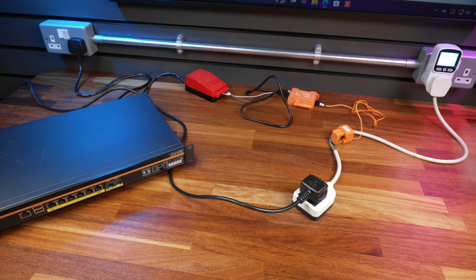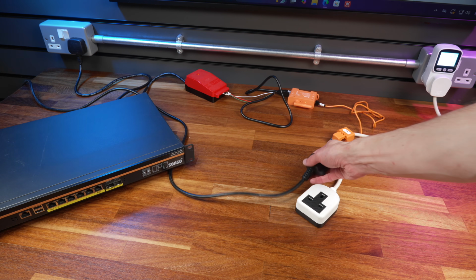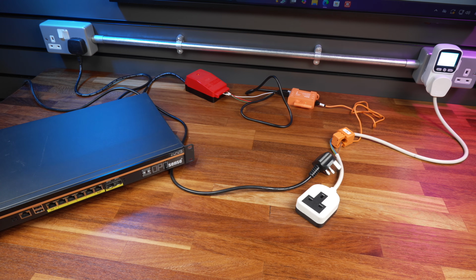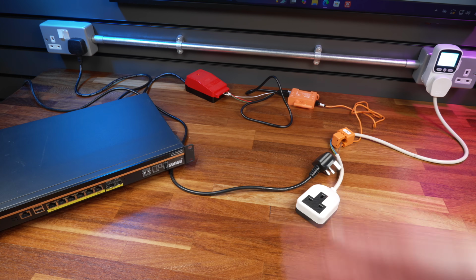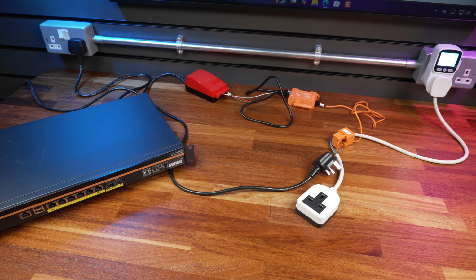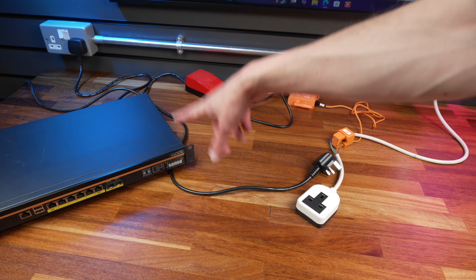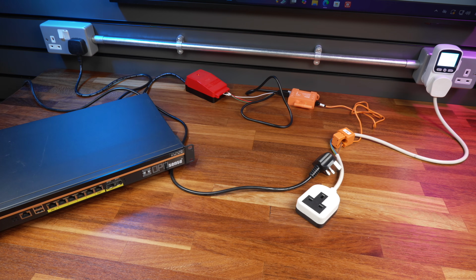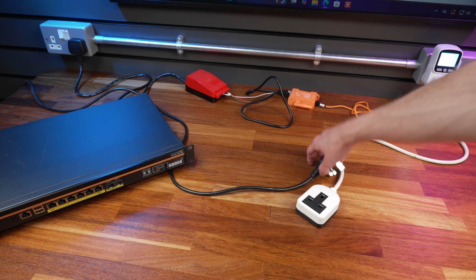So now what I want to do is test with something that's got a much worse power factor. I dug around trying to find a device that's got a really low power factor. Turns out that actually most modern stuff's pretty decent. Tried all sorts of power tools with big motors. They were all kind of power factor like 0.95 sort of thing. But then I found my old firewall, which does have a pretty poor power factor of 0.5 to 0.6. So pretty poor power factor. So if we plug this in, we can take a look at what we get for measurements.